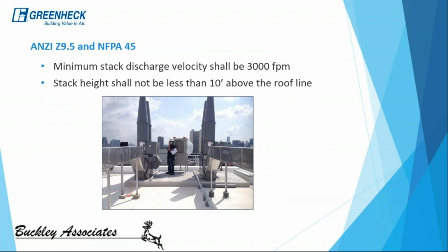So there are two main code requirements that apply to installing a lab exhaust fan. The first one is that the minimum stack discharge velocity needs to be 3,000 feet per minute. Some people now are seeing this, and code is changing over time as it always evolves. This number is actually going to be going away shortly. And even though the number is going to be taken out of code, it still doesn't mean we shouldn't pay attention to it. It's still a good guideline for what our discharge velocity should be right at the discharge of these fans.